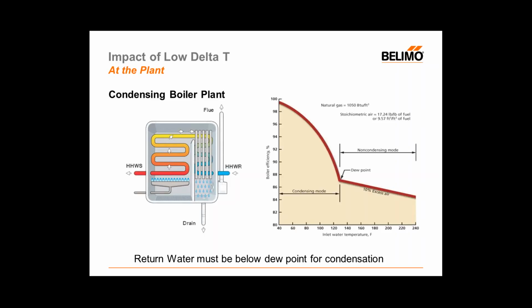And so this graph that we're putting up here, it's coming a little slowly, there it is, is courtesy of ASHRAE, but each condensing boiler manufacturer is going to produce a similar type graph that shows the efficiency of your boiler based on your return. They call it inlet, but they mean inlet to the boiler. So for us, it's the return water temperature, and as you get cooler and cooler, you get to the dew point inside of the condensing chamber, and then you can see there's a sharp increase in your condensing. So you can see on a graph like this, if they're condensing starting at 130 degree return water and we get down even just to 120 degrees, so 10 more degrees of delta T, we're taking efficiency from maybe 87 to 90 or 91%.